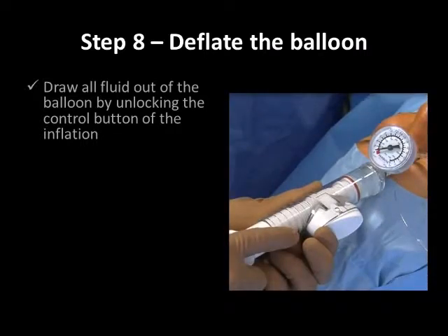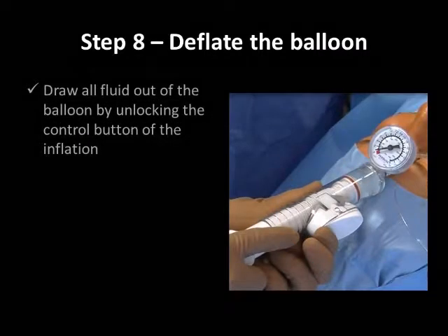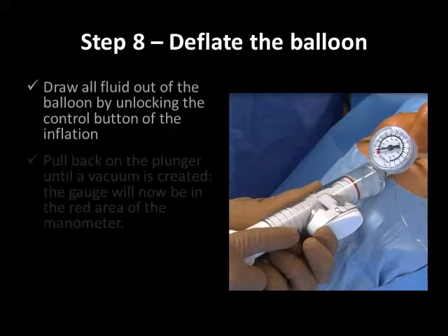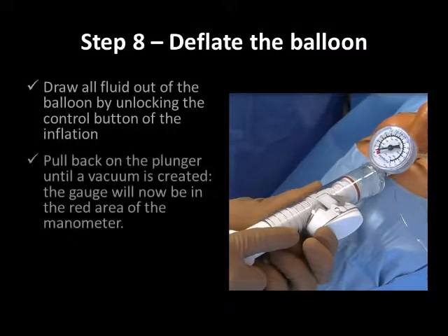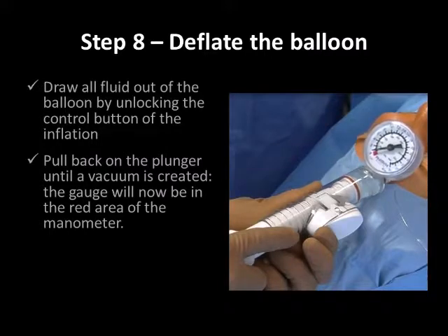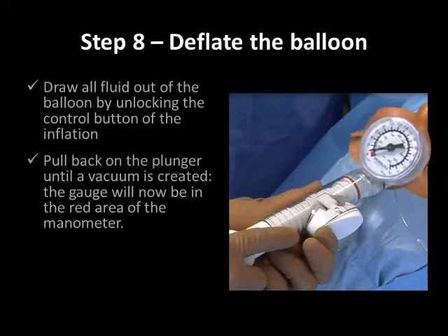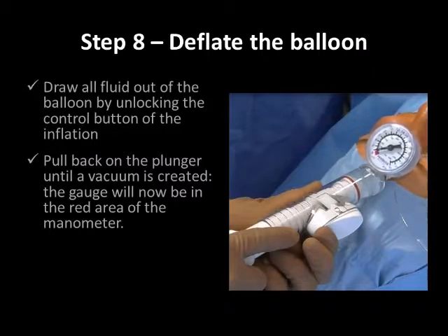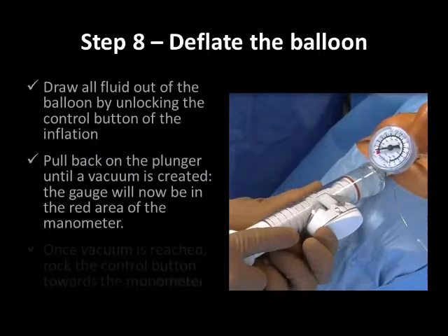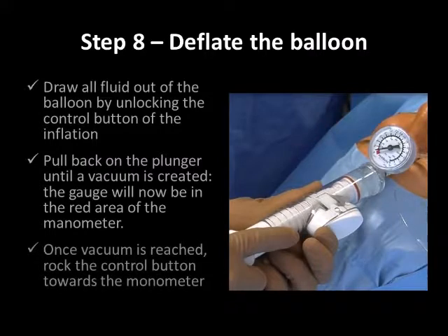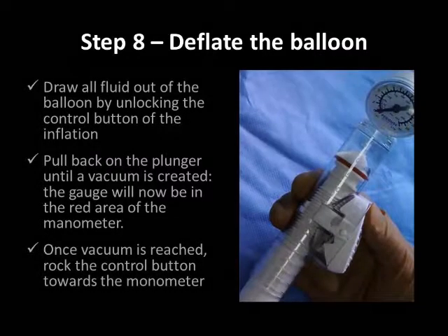Do this by unlocking the control button of the inflation device, in other words, rocking it toward the back of the plunger, opposite the manometer, allowing the plunger to move freely. Pull back on the plunger until a vacuum is created. You'll know a vacuum is created by looking at the gauge, which will now be in the red area of the manometer. Once vacuum is reached, lock the plunger by rocking the control button toward the manometer.